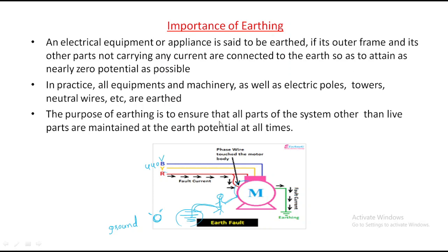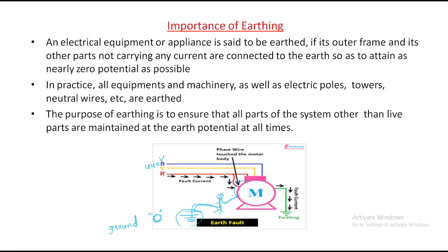The purpose of earthing is to ensure that all parts of the system other than live parts are at earth potential at all times. Live parts means these parts, this A phase and B phase. For example, if one phase is earthed to the ground, what happens? The complete current will flow only to the ground, and no power enters the motor. The motor will not work properly. That's why live phases are not given the earthing, because if you give the earth, the total power will travel to it. So only the non-live parts are maintained at earth potential at all times. Understand? Right.